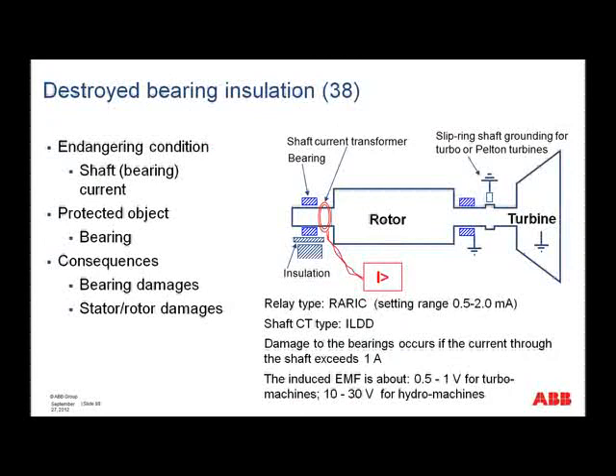And then finally, we can look at this destroyed bearing insulation. Okay, if you look at the picture, you can see that we have the bearing insulation, and this protection is really designed around this special shaft current transformer. Okay, and should the bearing be damaged such that we get current flowing in the shaft, this can be detected, because we can actually get damage to the bearings if this current exceeds about 1 amp.